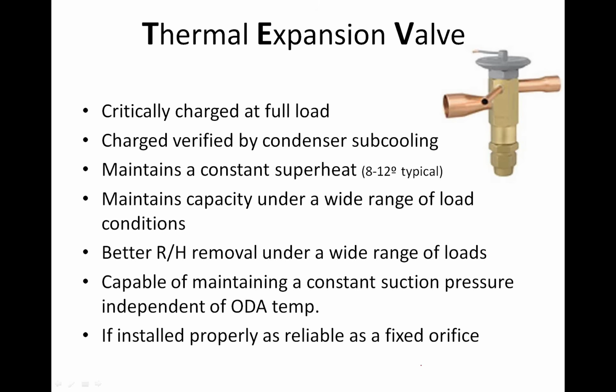but it does respond to changes in superheat. So if we were to drive up our outdoor air temperature, we'd also drive up our pressure. Well, that pressure is going to force more refrigerant into the evaporator. When we force more refrigerant into the evaporator, the superheat is going to drop, and as the superheat drops, the TXV closes to control the amount of superheat in the evaporator coil. If the TXV is installed properly, it's as reliable as a fixed orifice.